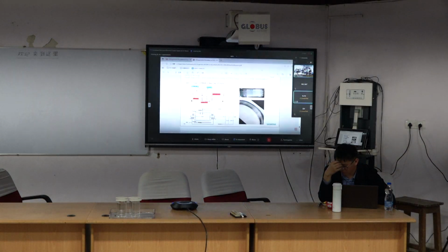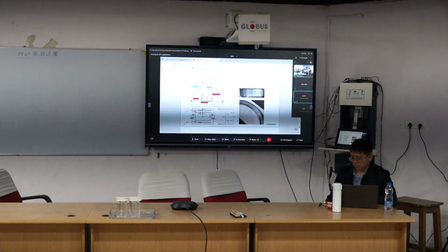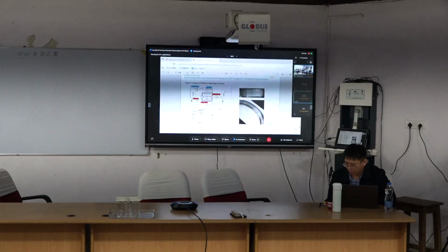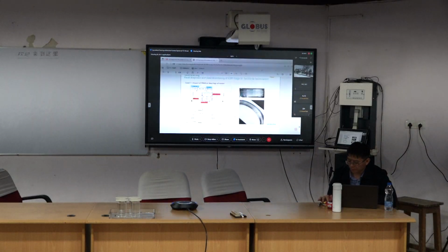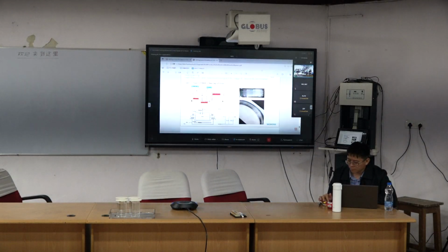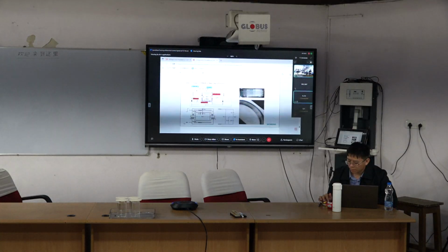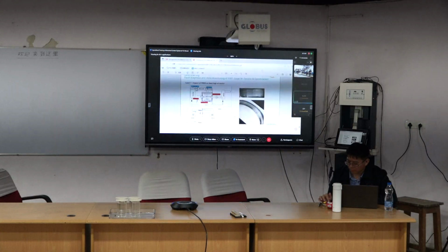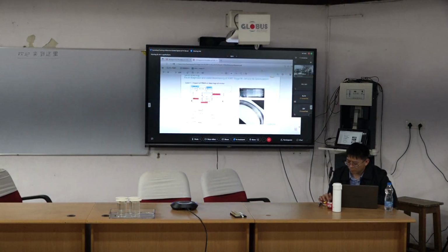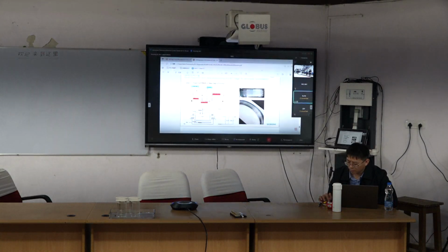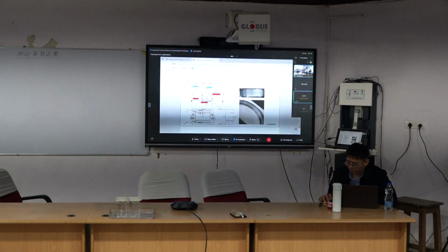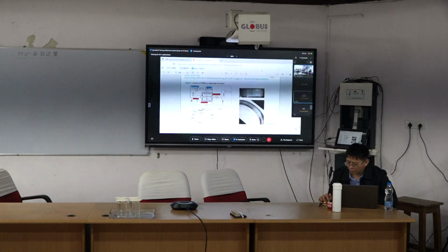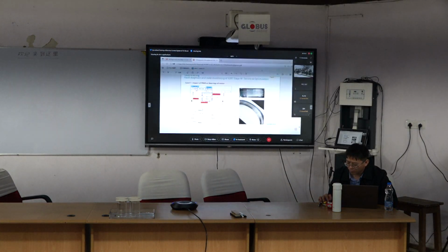This creates a kind of high frequency capacitive leakage current between the winding and housing, and thus to the ground. This leakage current leads to magnetic imbalance in the motor, which induces the high frequency shaft voltage, V shaft.